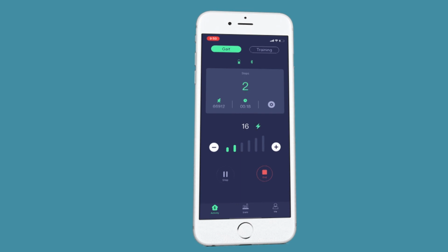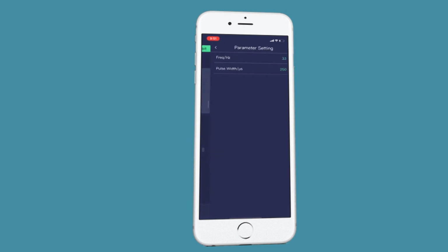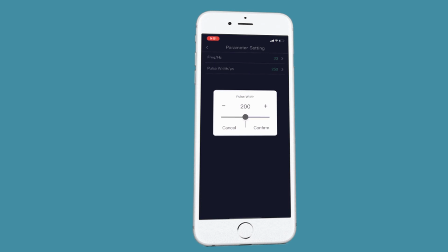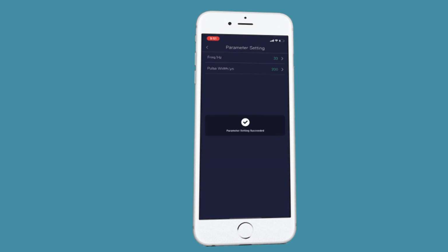You can see that it collects your steps. It gives you visual indication of when you're receiving stimulation. It shows you the amount of steps you've taken total, the duration of time that you've been walking, and of course you can make changes to the parameters. You notice when you hit stop, you have to hold the stop button for around 3 seconds for it to be able to stop. And then in the parameter settings, you see you can quickly change frequency and pulse width to make the stimulation more appropriate, more comfortable for you.